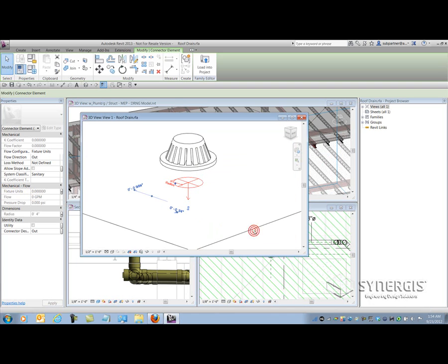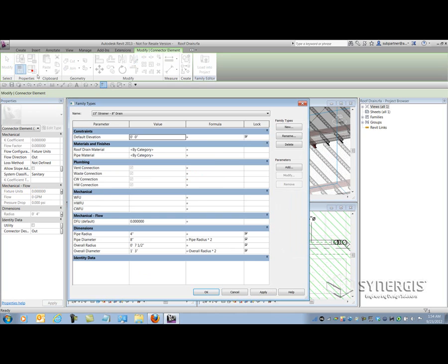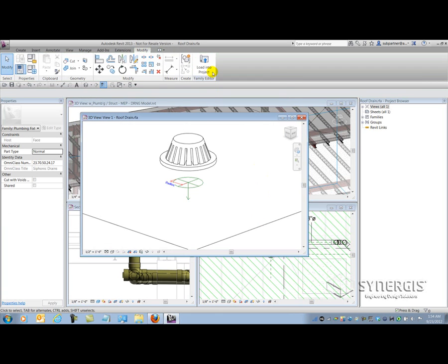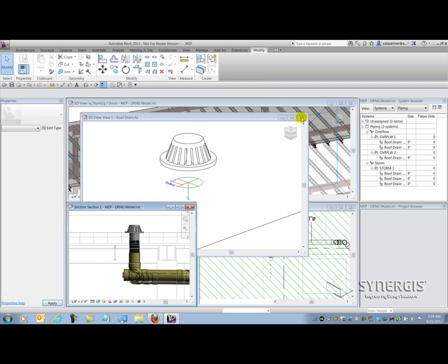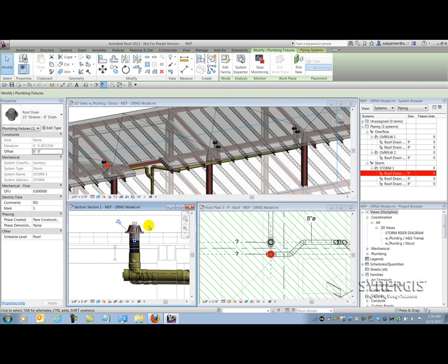Hitting OK one more time, I can go up to Family Types on the ribbon and look at the new parameter I created called DFU. It's set to default, which means it's an instance parameter, so I'll be able to provide a value for each and every drain. I select OK and load that into my project, overwrite the existing version, and close down the family itself. Picking that drain now, I can see the new parameter DFU — it's shared to the family and I can actually interact with it now.